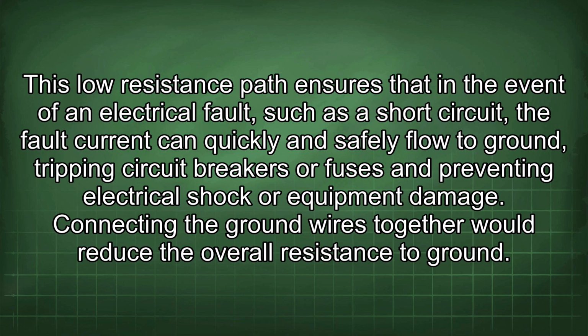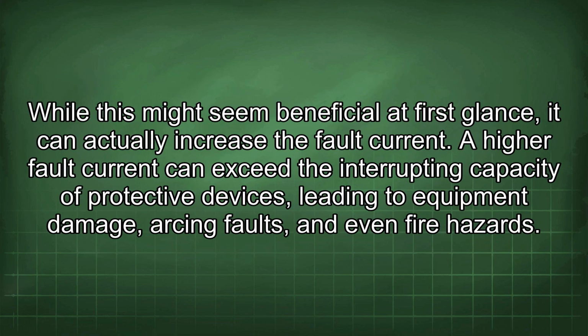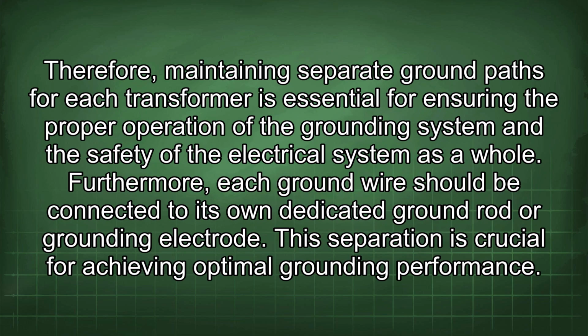Connecting the ground wires together would reduce the overall resistance to ground. While this might seem beneficial at first glance, it can actually increase the fault current. A higher fault current can exceed the interrupting capacity of protective devices, leading to equipment damage, arcing faults, and even fire hazards. Therefore, maintaining separate ground paths for each transformer is essential for ensuring the proper operation of the grounding system and the safety of the electrical system as a whole.